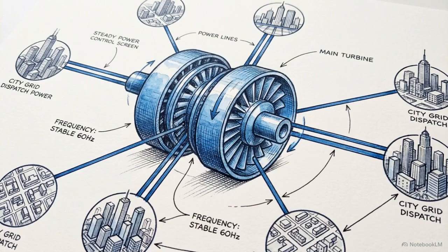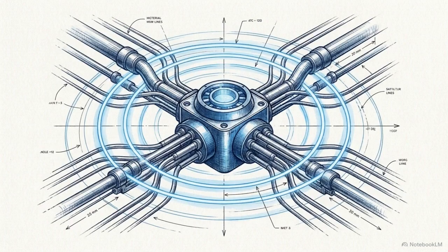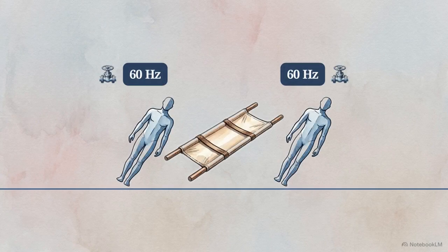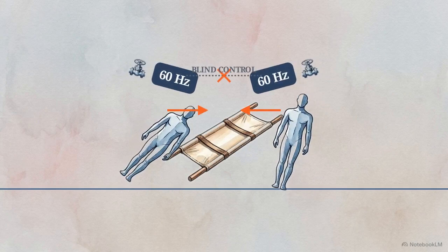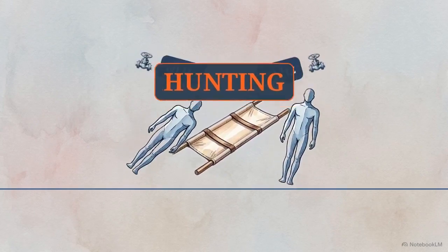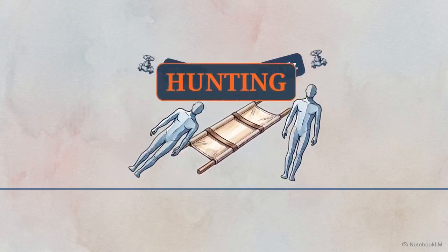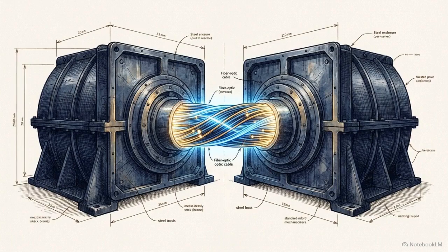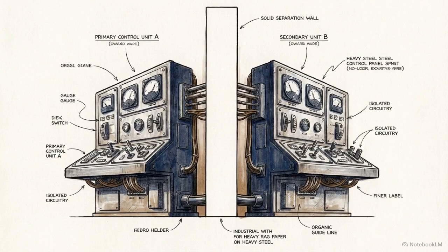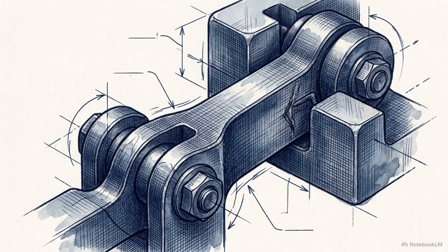Isochronous mode works when only one unit is active, because that single generator serves as the undisputed anchor for the grid. It dictates the frequency, and the grid follows. This illustration shows two people carrying a single stretcher. If both individuals are rigidly insisting on dictating the exact pace, they will fight each other with every single step, unless there is a dedicated, active digital load-sharing network installed between the packages. Two isochronous controllers are completely blind to each other's outputs. They only see the frequency, attempting to force it to their own reference point.